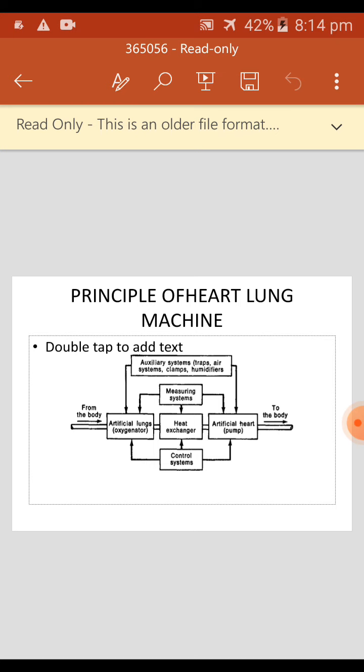Next, principle of the heart-lung machine. Centrifugal pumps use forces to transport blood instead of tubing compression. Because of the technical principle of operation, the centrifugal pump has limited application. Centrifugal pumps have the advantage of delivering limited amounts of air, causing less blood damage in the long run. An additional flow meter is required to determine the delivered flow, which is a disadvantage.